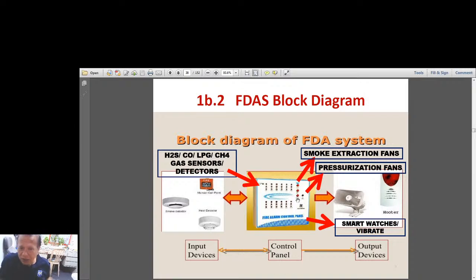And the control panel, since it is a logic device, will send a signal to your buzzer and light and horn or whatever to actuate an alarm. And you can also automatically operate smoke extraction, air pressurization, and others. Of course, here I have included in my suggestion the provision of toxic gas detectors, which is my baby, like I said. Carbon monoxide and hydrogen sulfide are toxic gases, and LPG is highly flammable, and of course CH4 is methane, highly flammable. So these detectors must be provided so that we can ensure a higher level of safety for our buildings and facilities.